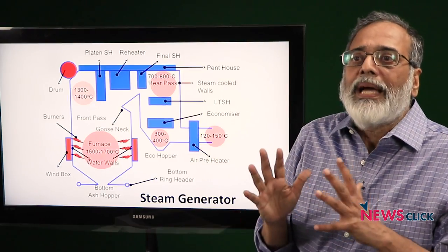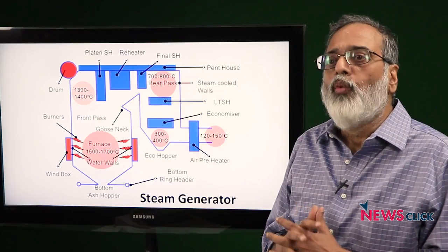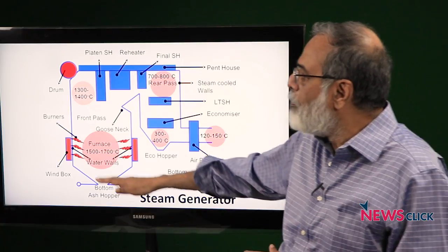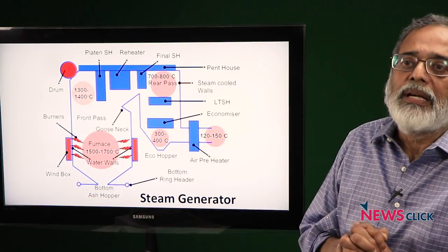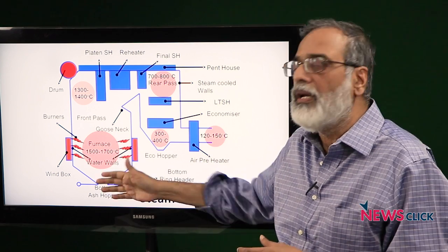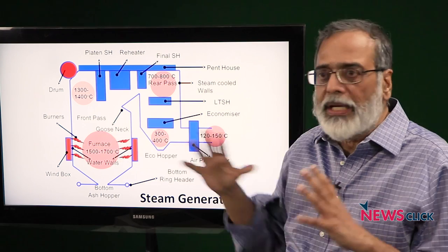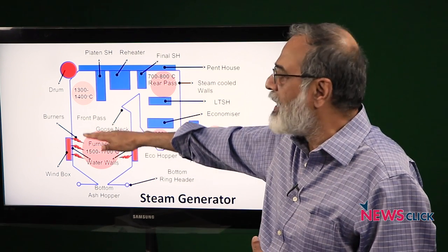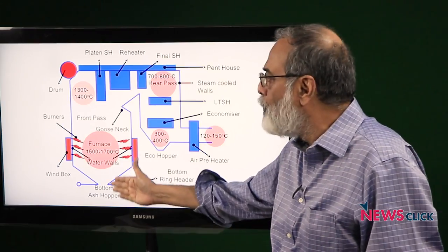The attempt by NTPC officials was to bring down the load of the unit while trying to manually see whether they could stop the clinkering or remove the clinkers from the bottom side of the boiler. When you bring down the load, clinkering may reduce but if clinkering has already taken place and there is a lot of ash build up, then removing it is not easy.